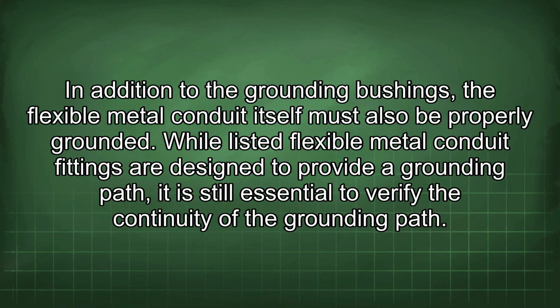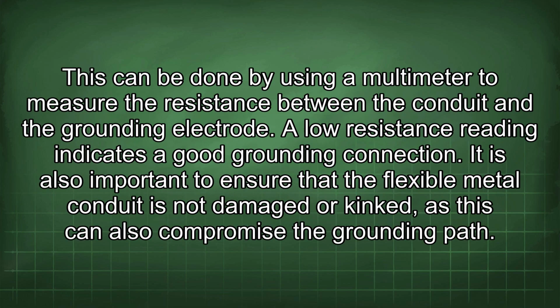In addition to the grounding bushings, a flexible metal conduit itself must also be properly grounded. While listed flexible metal conduit fittings are designed to provide a grounding path, it is still essential to verify the continuity of the grounding path. This can be done by using a multimeter to measure the resistance between the conduit and the grounding electrode. A low resistance reading indicates a good grounding connection.